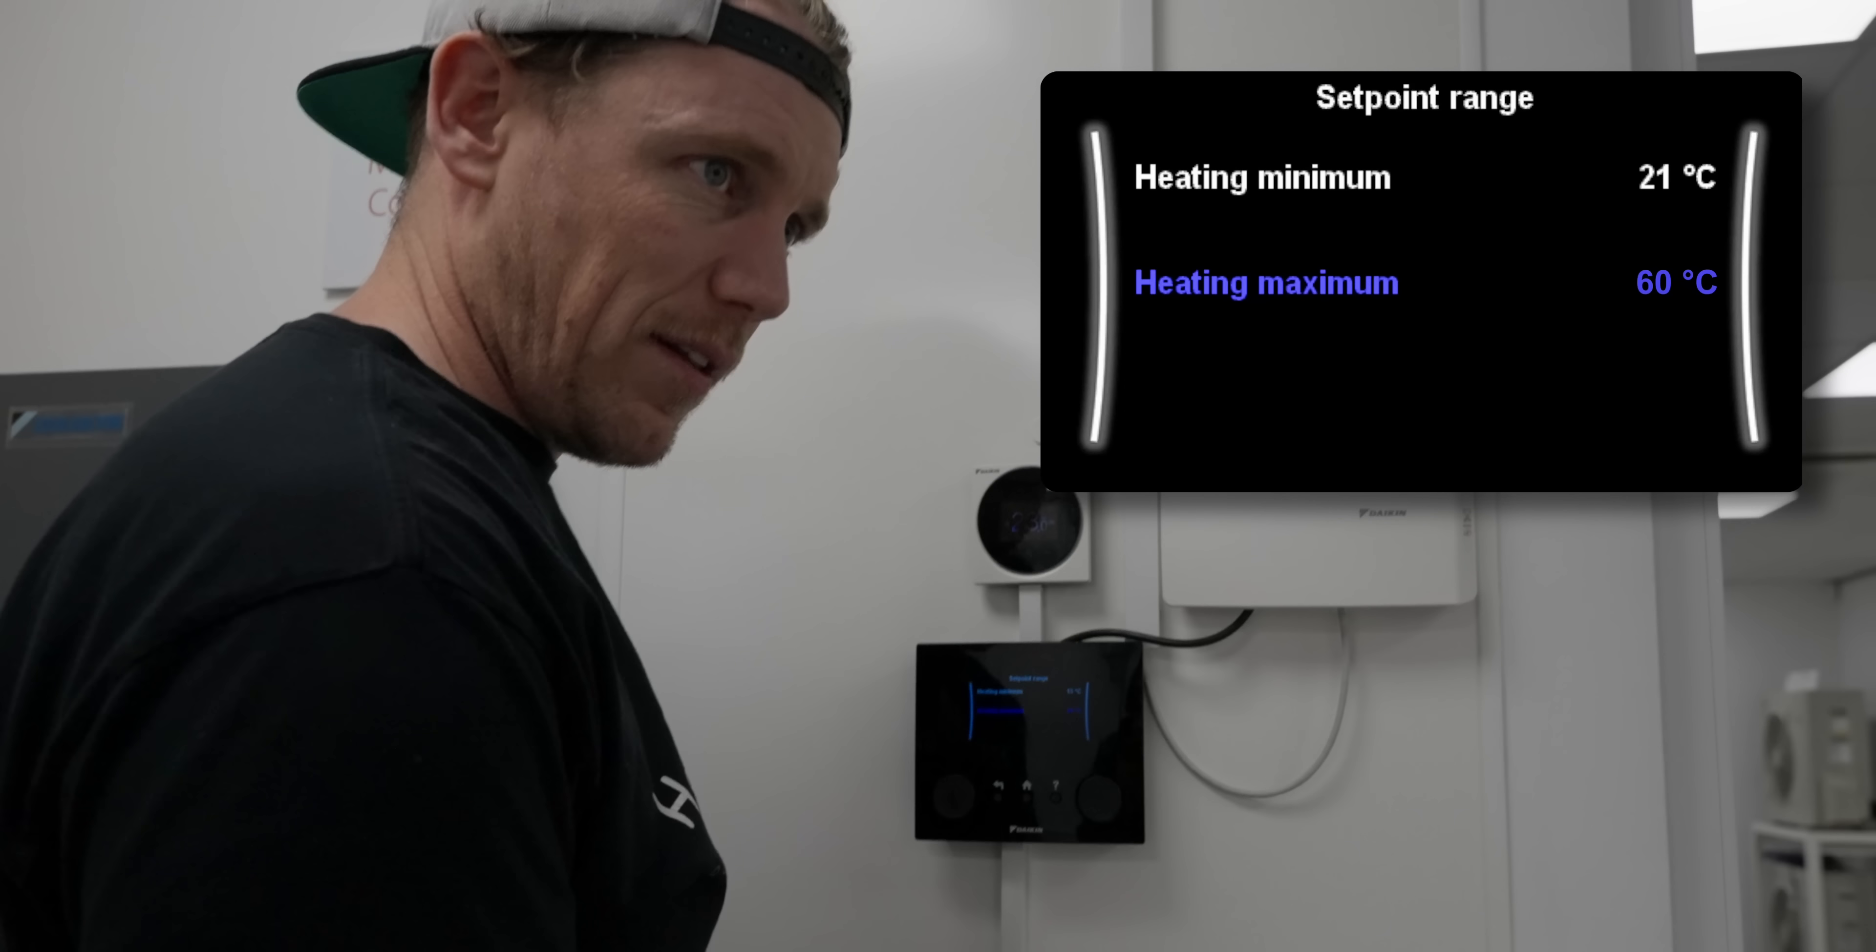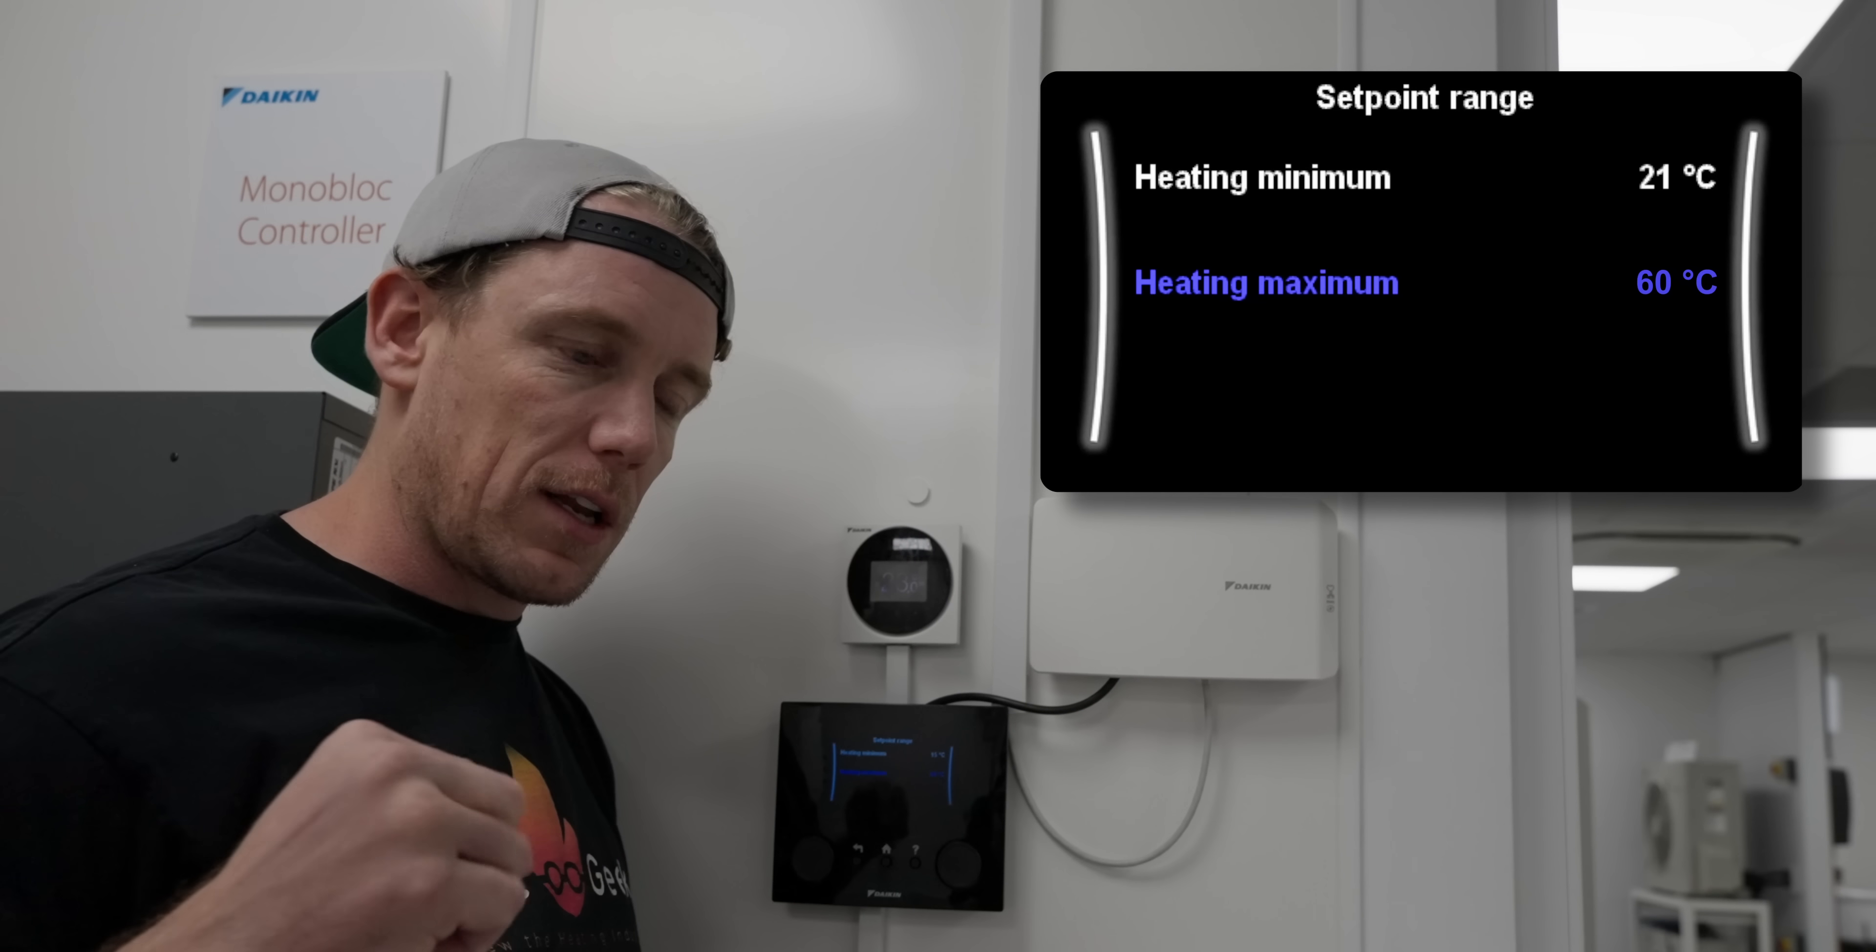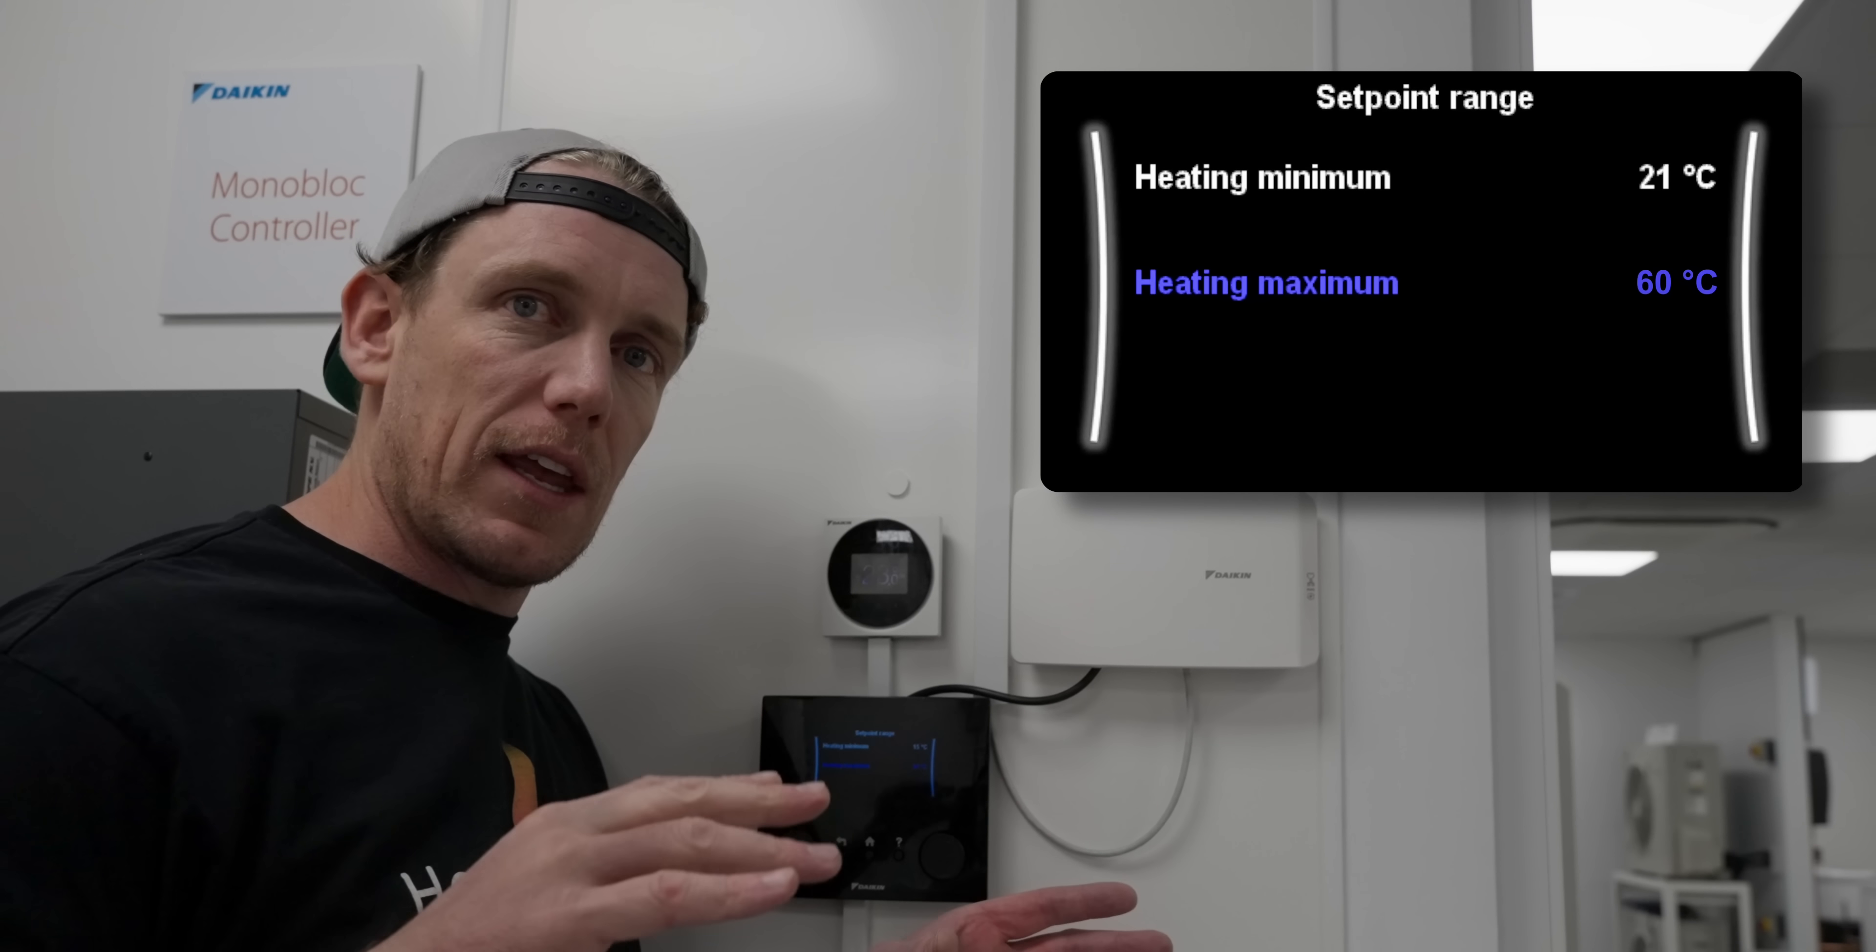Some other heat pump manufacturers, Viessmann and Vaillant for example, potentially Nibe, they track this hot water store temperature and you can set your flow temperature to X degrees above the store temperature to slowly and gently heat it.